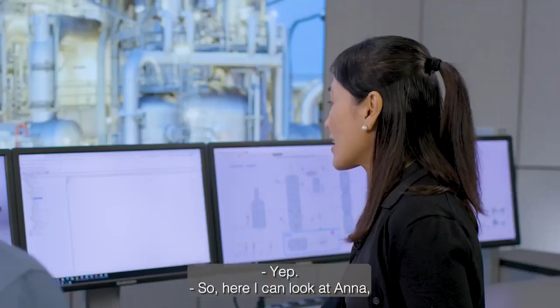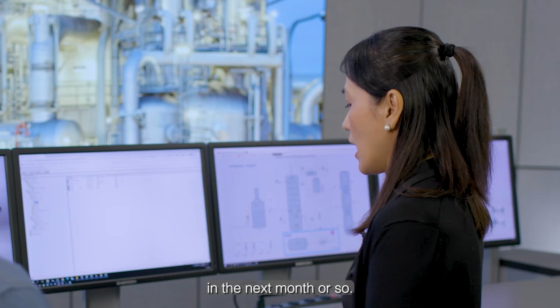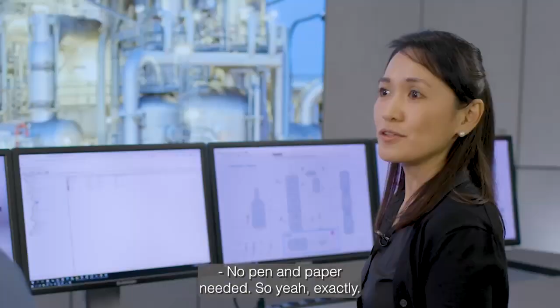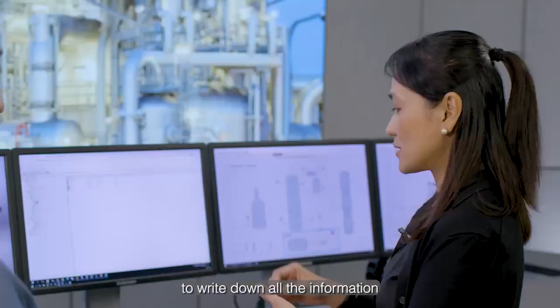Yep. So here I can look at Anna. I have all these devices that I need to calibrate in the next month or so. I just check out that route into the calibrator. I go to the field, do whatever calibration work that I need to do, and then go back into Device Manager and check in my calibrator so that it would transfer all the information into AMS Device Manager. Wow, no pen and paper needed. No pen and paper needed. So yeah, exactly. Tin was showing you all those pen and paper to write down all the information that he did in the field. Yep.